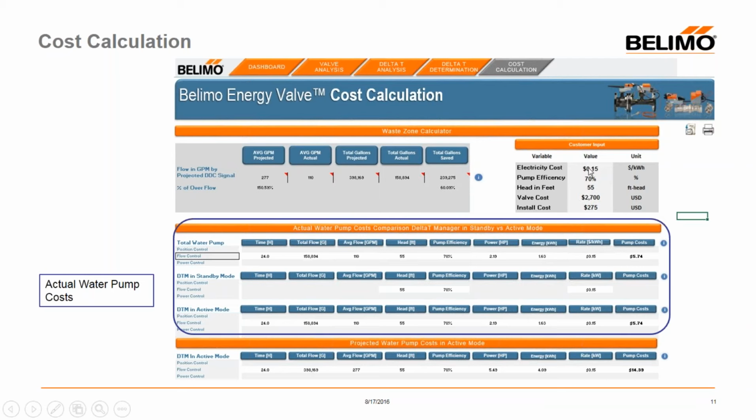Customer input, you're going to put in your utility costs, your pumping efficiency, and your head in feet. And we're going to take those values down here, and we're going to calculate what it actually costs to pump water through that valve for the time period selected.